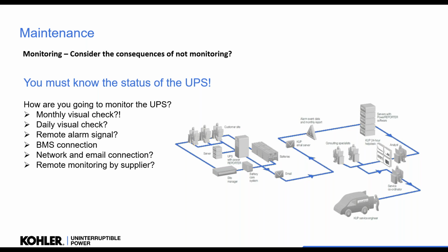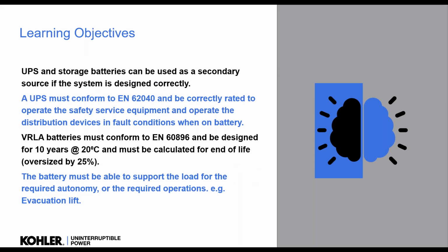Okay. So hopefully, the learning objectives out of this: we can use UPS as storage batteries as a secondary source if it is designed correctly. Okay, very important. The UPS must conform to 62040, correctly rated to operate the safety services, start them up, and trip the distribution devices in fault conditions when running on battery. Not always done. The VRLA must conform to 60896, must be and should be designed for 10 years at 20 degrees, and really should be calculated for end of life. So when we get to replacing them, it should still be doing the autonomy we require. Okay? And we must be able to support the load for the required autonomy.